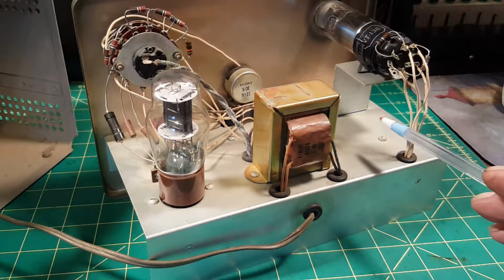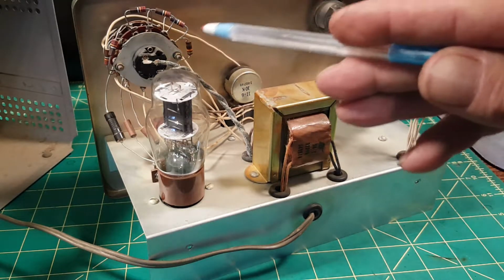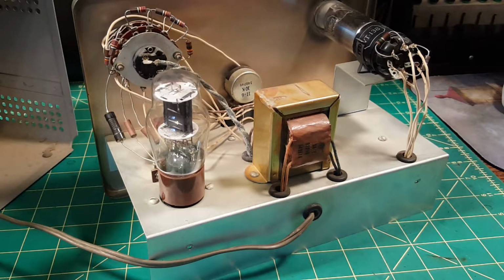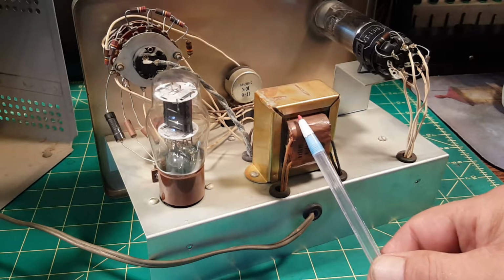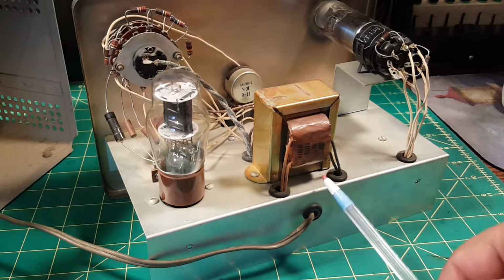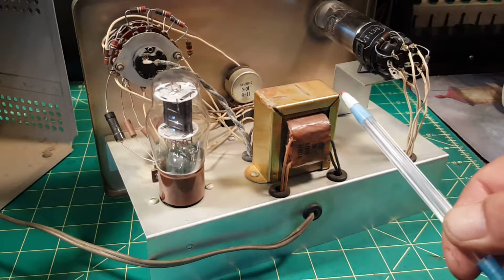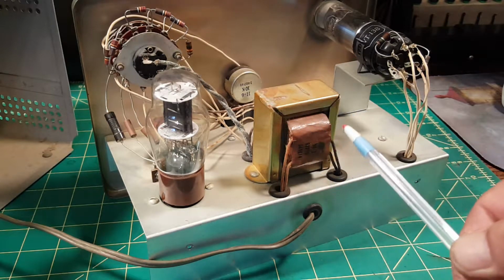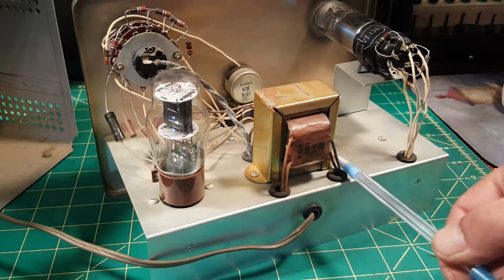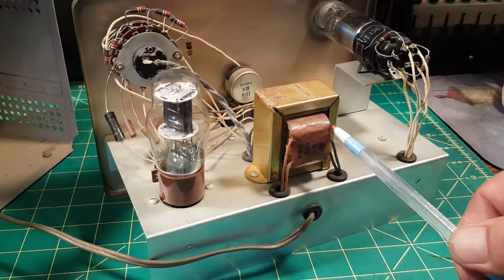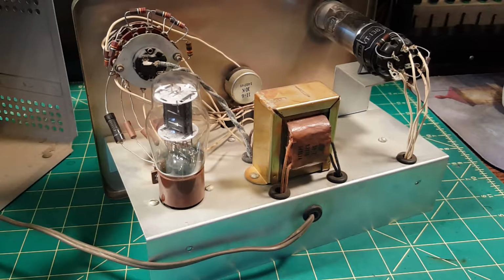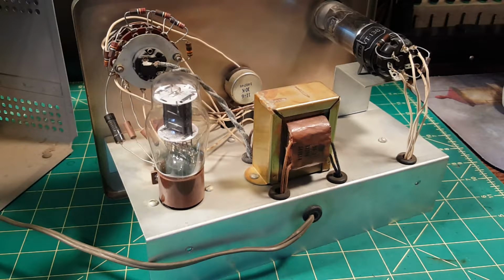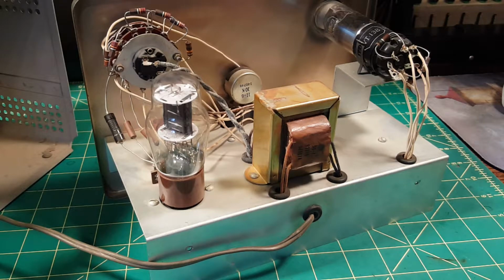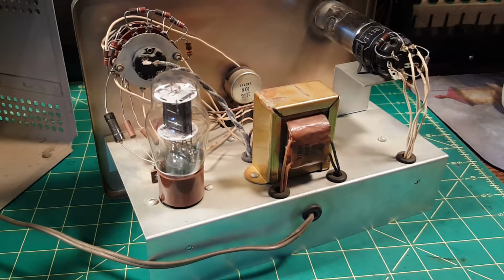That's what I'm looking for first - corrosion, especially on transformer cores. On this one you can't see the exposed E&I laminations since they're covered by this cover, but looking inside here, the varnish looks new, it's present, it's not flaked off, and there's no sign of rust anywhere.